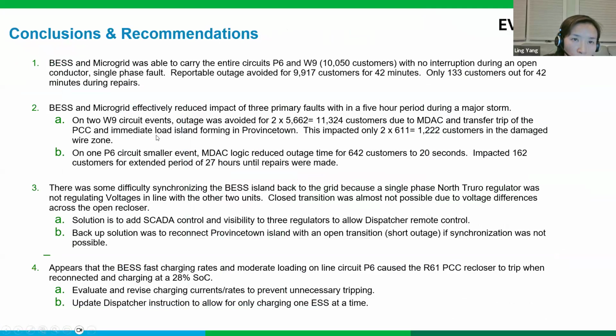So these are the conclusions and recommendations based upon some of the events in the field and some of the lessons learned. One is that the battery and the microgrid are able to pick up the customers as designed, and it greatly improves the customer interruption index. This calculates how much the system performance improved. Also, during one of the events, we found there was some difficulty synchronizing the battery island back to the grid because of the unbalance, and also the tap was stuck at one of the voltage regulators. That delayed the synchronizing of the BESS back to the grid.